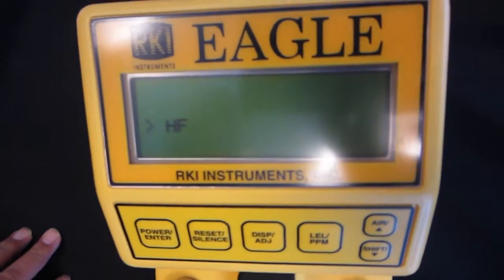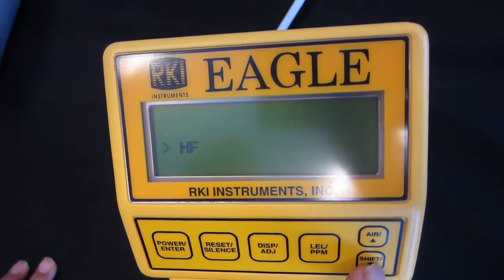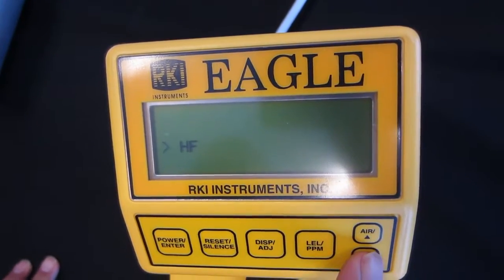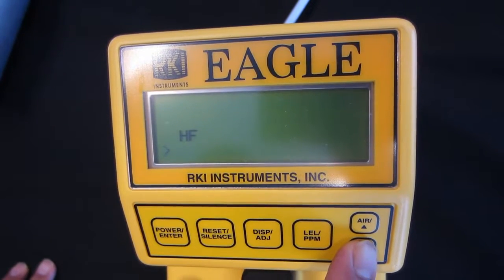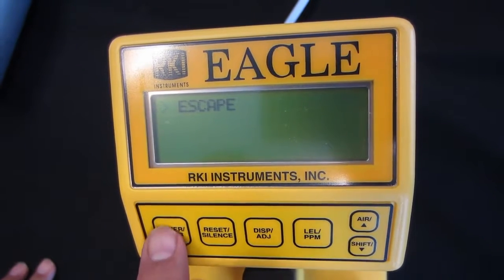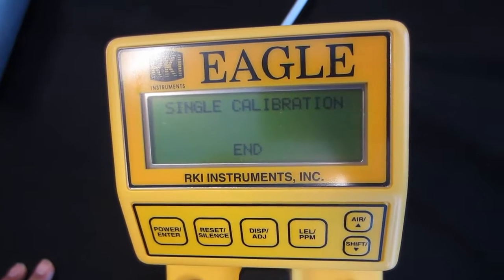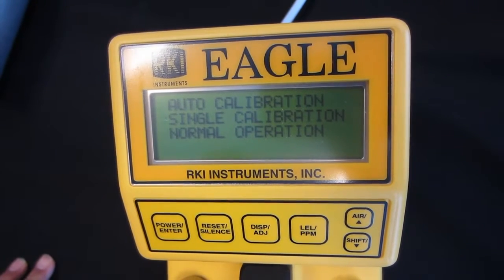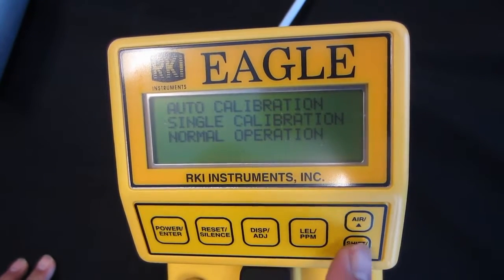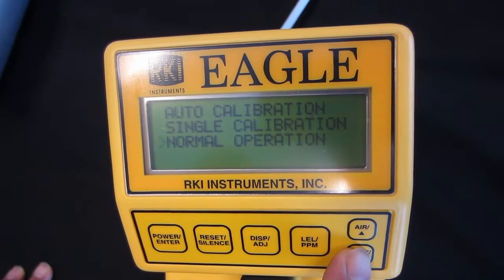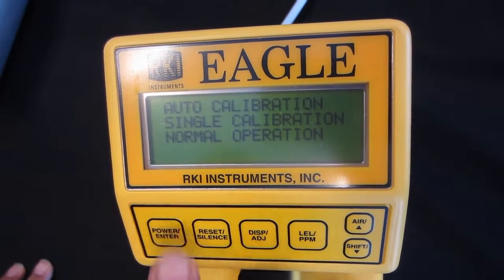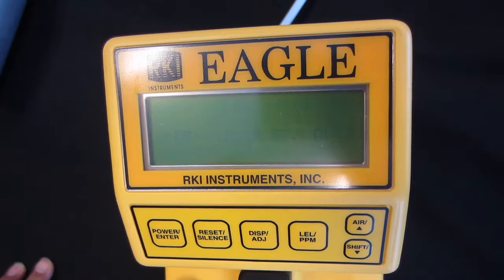Okay, so going back to the display, we're back to the cursor flashing at HF. At this point, we want to use our down arrow key and take the cursor to the word escape, and then press power enter at that point. And that's going to bring us back to the calibration menu, at which point we move down to normal operation, press power enter, and that brings us back to normal operation in the instrument.